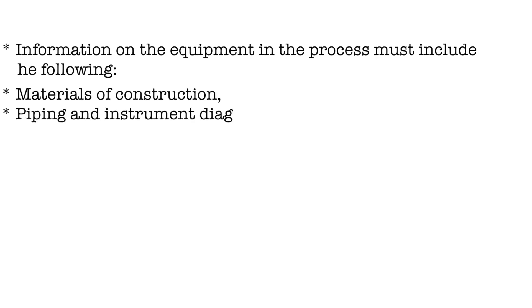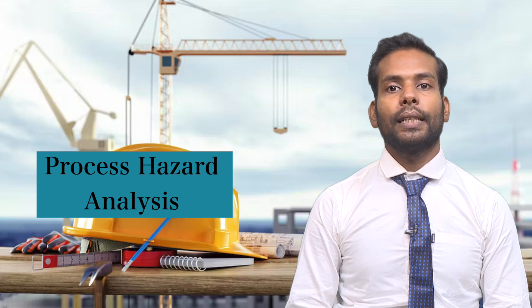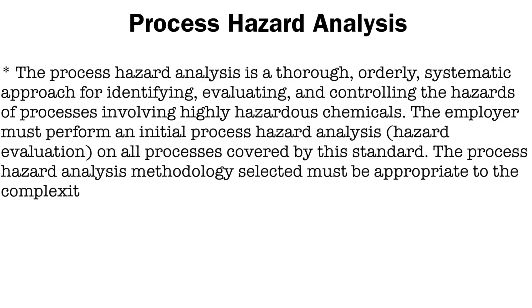Information on the equipment in the process must include: materials of construction, piping and instrument diagrams, electrical classification, relief system design and design basis, ventilation system design, design codes and standards employed, material and energy balances for processes built after a certain date, and safety systems such as interlocks, detection, and suppression systems.